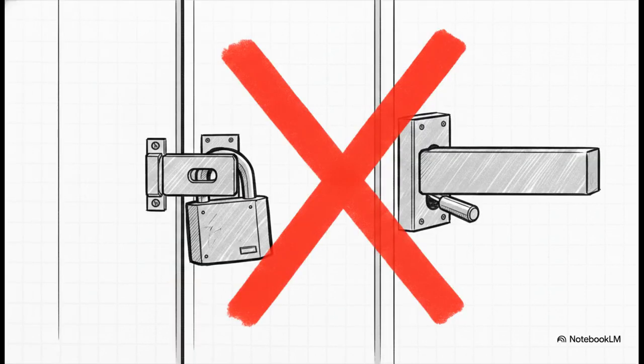But here's the catch. Human error cannot be allowed to compromise that structural integrity. So physical access control steps in to back up that IEC standard. You'll see main breaker doors carrying heavy-duty padlocks or safety key locks. But here is the critical, non-negotiable rule of marine electrical safety. The breaker can only be racked in or out when the door is securely closed and auxiliary voltage is connected. In fact, mechanical interlock bars actually slide into place to physically block you. There is absolutely no open door racking allowed, ever.